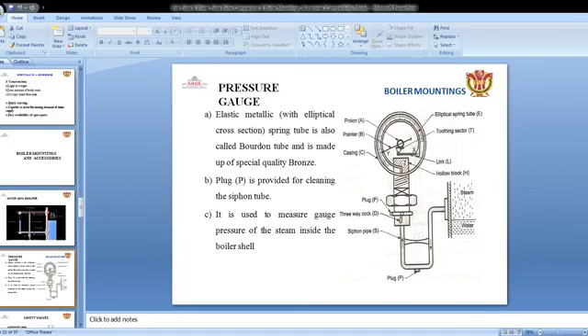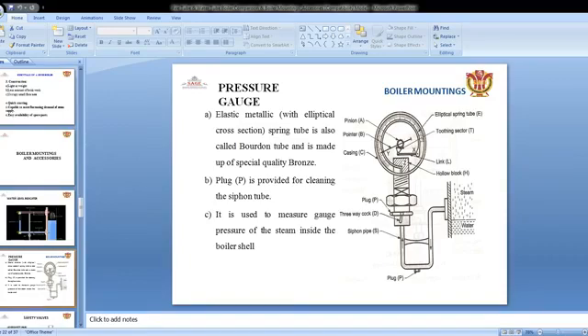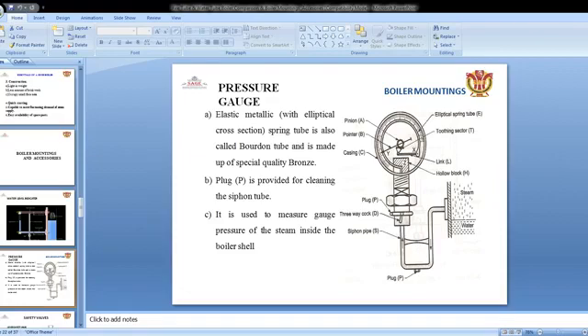The pressure gauge is a very necessary component of the boiler. It is an elastic metallic type with an elliptical cross section, also called a Bourdon tube. The Bourdon tube type pressure gauge is used. A plug is provided for cleaning the siphon tube, and it is used to measure the gauge pressure of the steam inside the boiler shell.